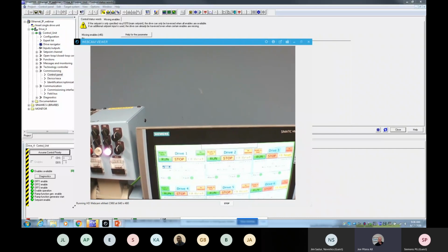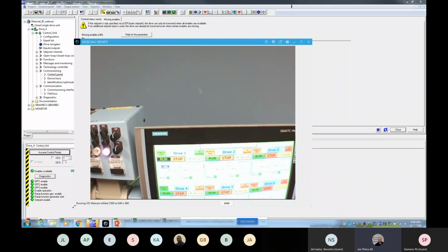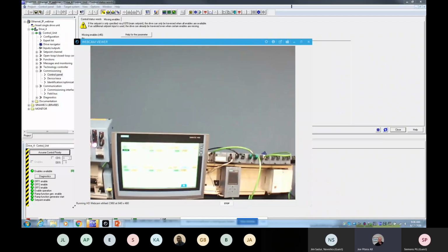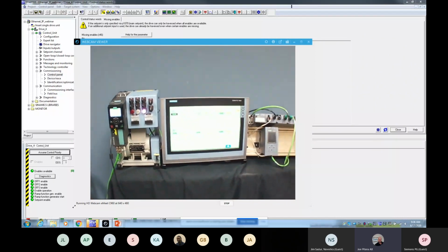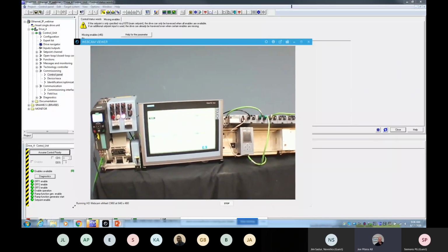And if I stall it out, you can see that a speed deviation alarm popped up immediately. And if I hold it tighter even longer, I'm going to get it to fault out. But we are getting additional data from the drive right to the HMI through a standard telegram and a standard block inside the PLC. I can stop the drive from there.